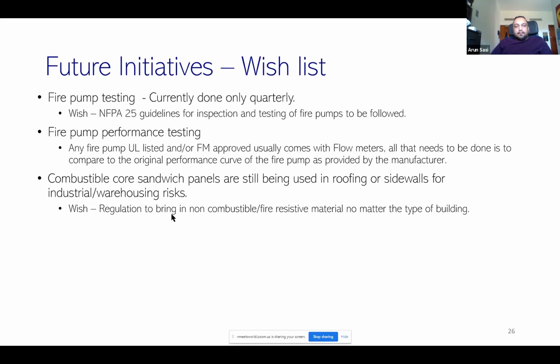So I think fire pump performance testing is again a way to figure out if the performance of the fire pump has gone down. This can usually only be done with FM approved or UL listed pumps, because you need flow meters, and you need to compare. So even if I do a fire pump performance test, I need to compare it with the original curve from the factory. A lot of the clients I visit never have the original curve as provided by the manufacturer.